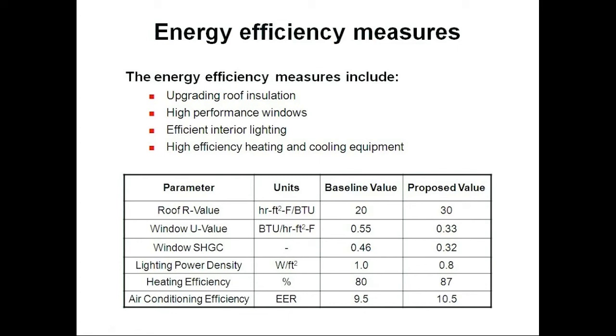Now that we have our proposed building defined, we can look at the results. Here you see the result of our proposed building model — heating and plug loads are the major energy end-use characteristics, and lighting is the next one. But because we're in Madison, Wisconsin, cooling is not nearly as high. You can also see that the most electric demand happens in the summer, as you'd expect, and the most natural gas usage happens in the winter. Very intuitive.